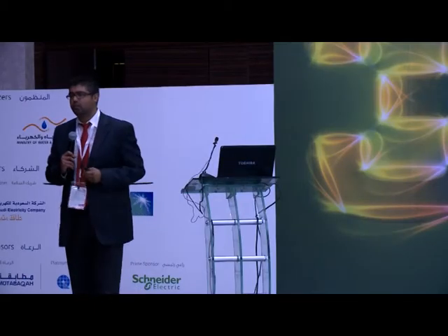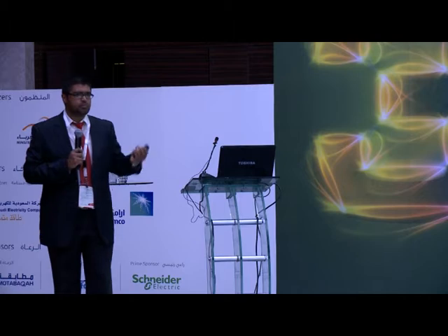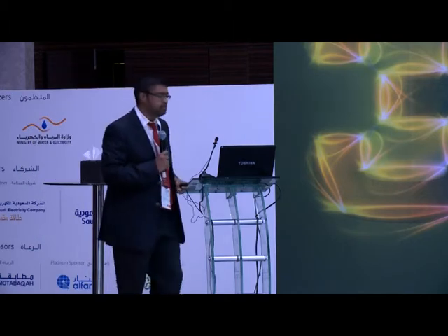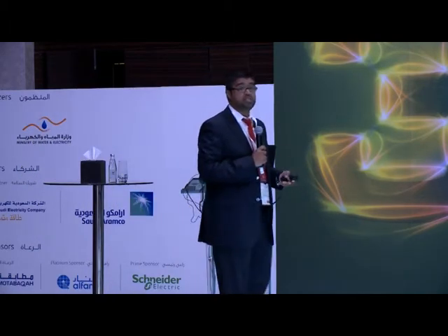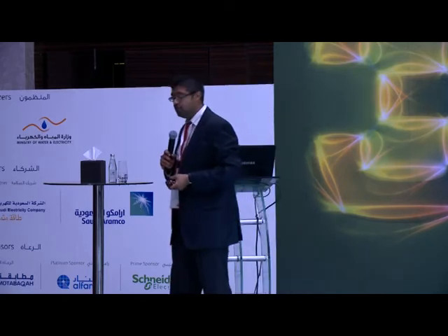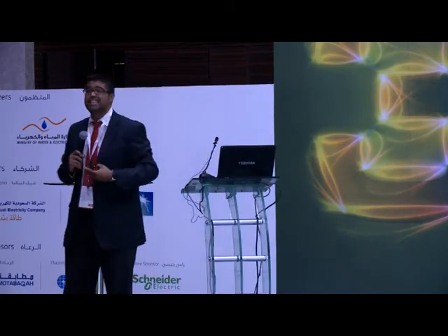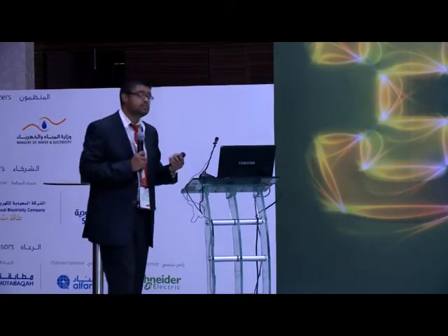Habit number 2 is always establish worker boundaries. Now, we've also spoken about boundaries. You've seen in the exhibition boundaries. We speak about limited, restricted. Those are the shock boundaries. And we speak about an arc flash boundary, which is a boundary at which the energy from the arc decreases to 1.2 calories per centimeter squared. I will elaborate on this a little later.